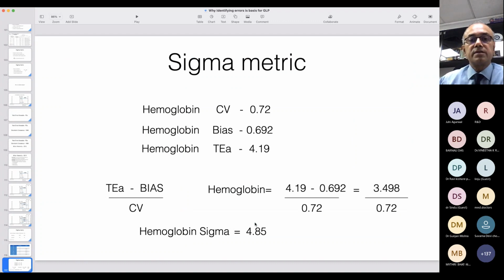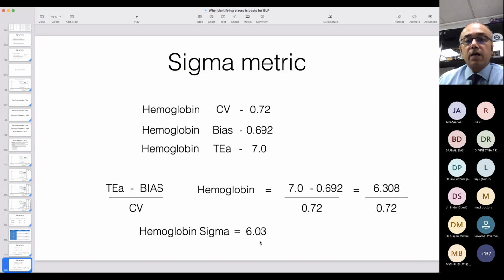I've given an example here. The hemoglobin CV is 0.72, bias is 0.692, and total error allowable is 4.19. So the sigma here would be 4.19 minus 0.692 divided by 0.72, which is 4.85. Now with the same CV and bias, but the TEA, total error allowable, changed to 7, you see how the sigma goes up to 6. It becomes world class.